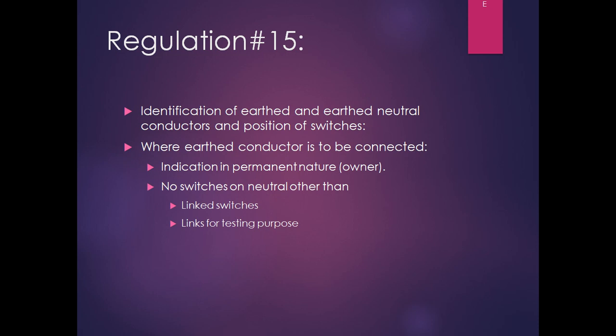This is generally required because the neutral conductor is connected with earth, and sometimes, to ensure the healthiness of the circuit, insulation resistance is to be checked. When you are checking the insulation resistance, if you do not disconnect the neutral wire from the earth wire, you will get a zero value. These links are used to disconnect the neutral wire from earth.